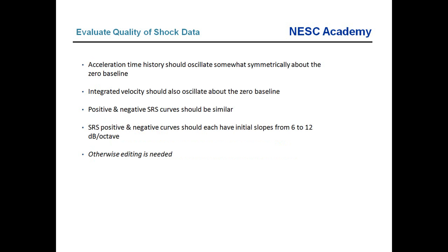Okay. Now, there's a couple of things that we do to try and judge the validity or quality of our accelerometer data. We expect our acceleration time history to oscillate somewhat symmetrically about the zero baseline. And then as we integrate that signal to velocity, we also expect the velocity to oscillate about the zero baseline, or at the very least have a net zero velocity. The positive and negative SRS curves should be similar, let's just say within 3 dB at all natural frequencies.